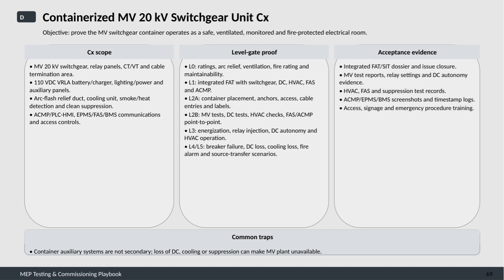Safety and operational systems like the arc flash relief duct, cooling unit, smoke and heat detection, and clean suppression are all part of this scope. Lastly, control and communication systems such as the ACMP or PLC-HMI, EPMS, fire alarm system, building management system communications, and access controls are critical components.